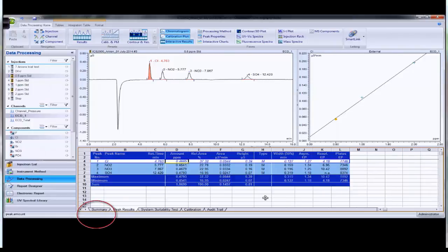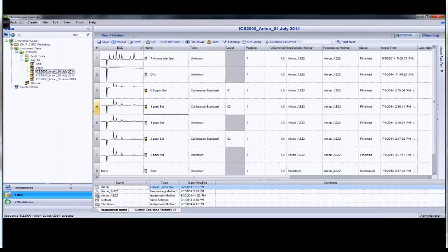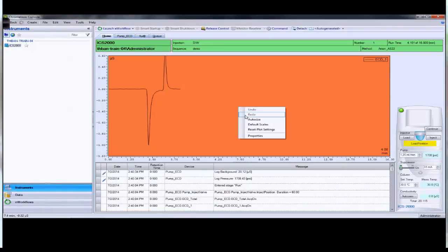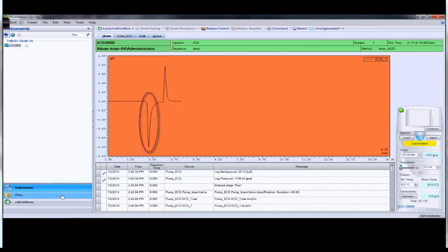Okay, so come down to the bottom left. As you get there, the Chromeleon icon will appear. You see there are two windows, Data and Chromeleon Studio. Click Data, and then click the instrument, and you've got our actual chromatogram. First thing here is the water peak, that first negative peak. That shows everything is working. And then we get the other peaks we're interested in.